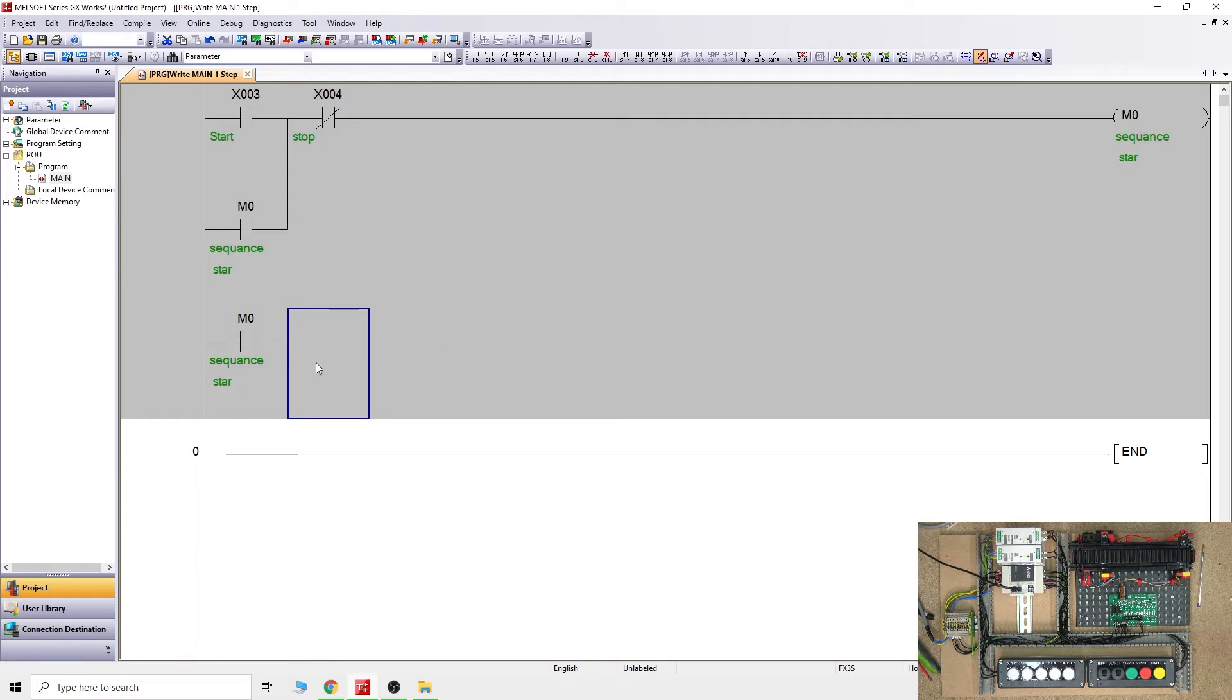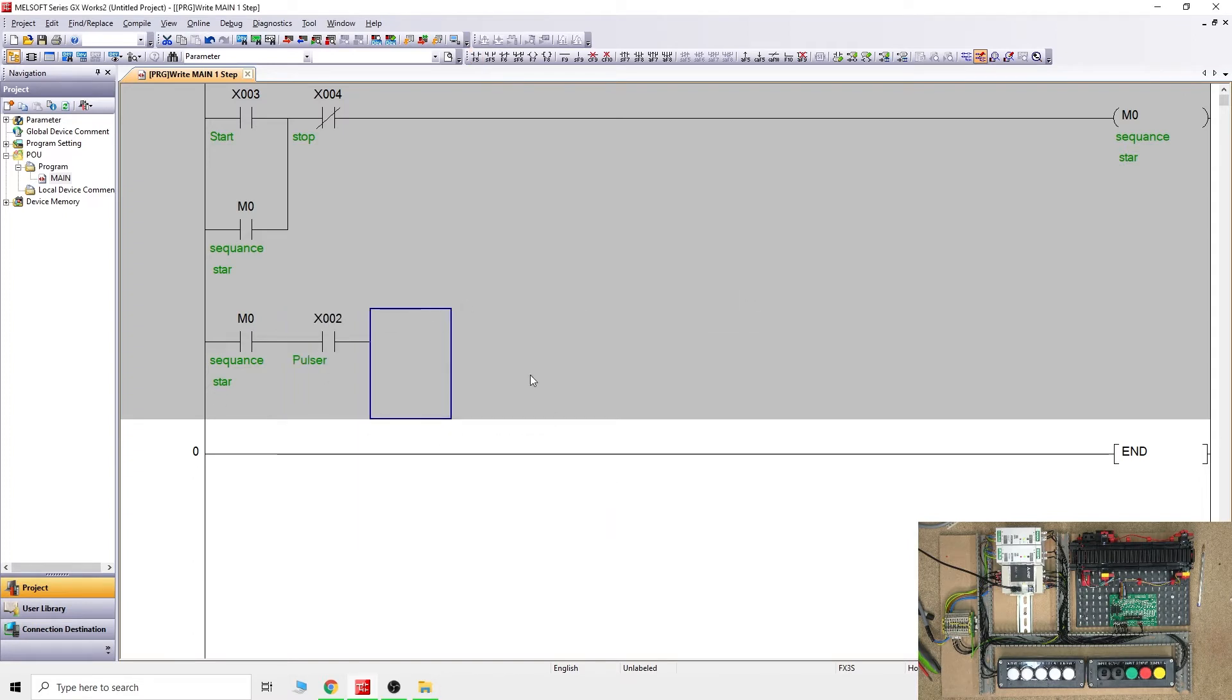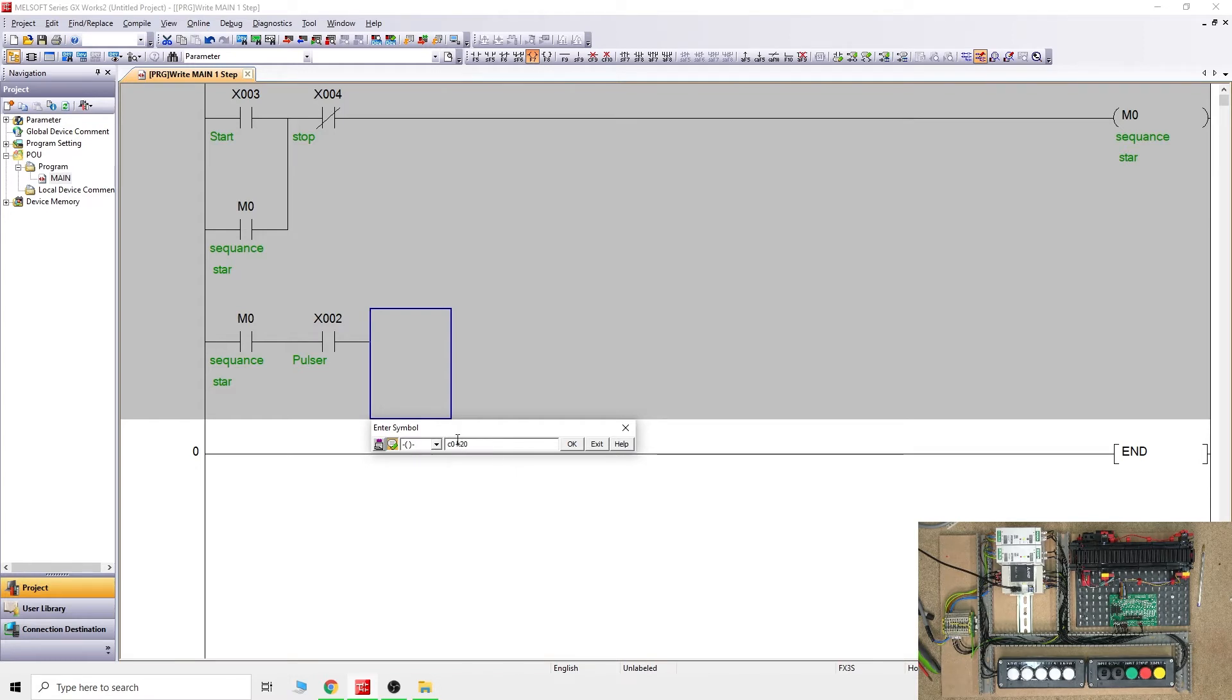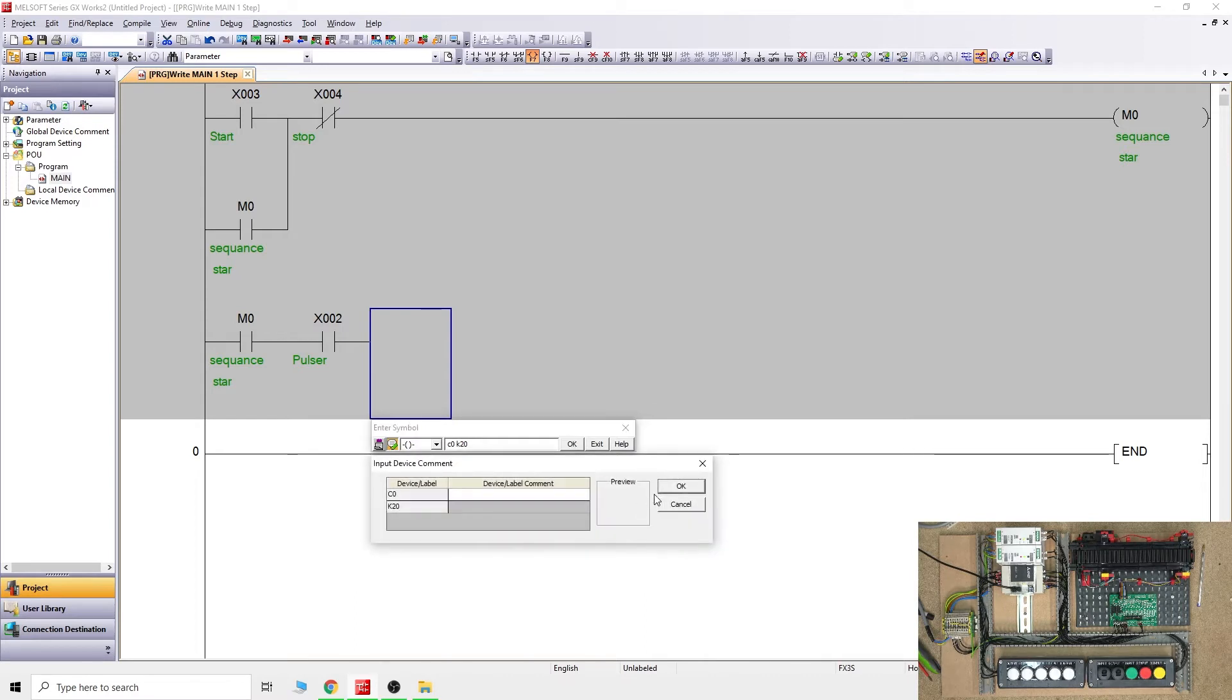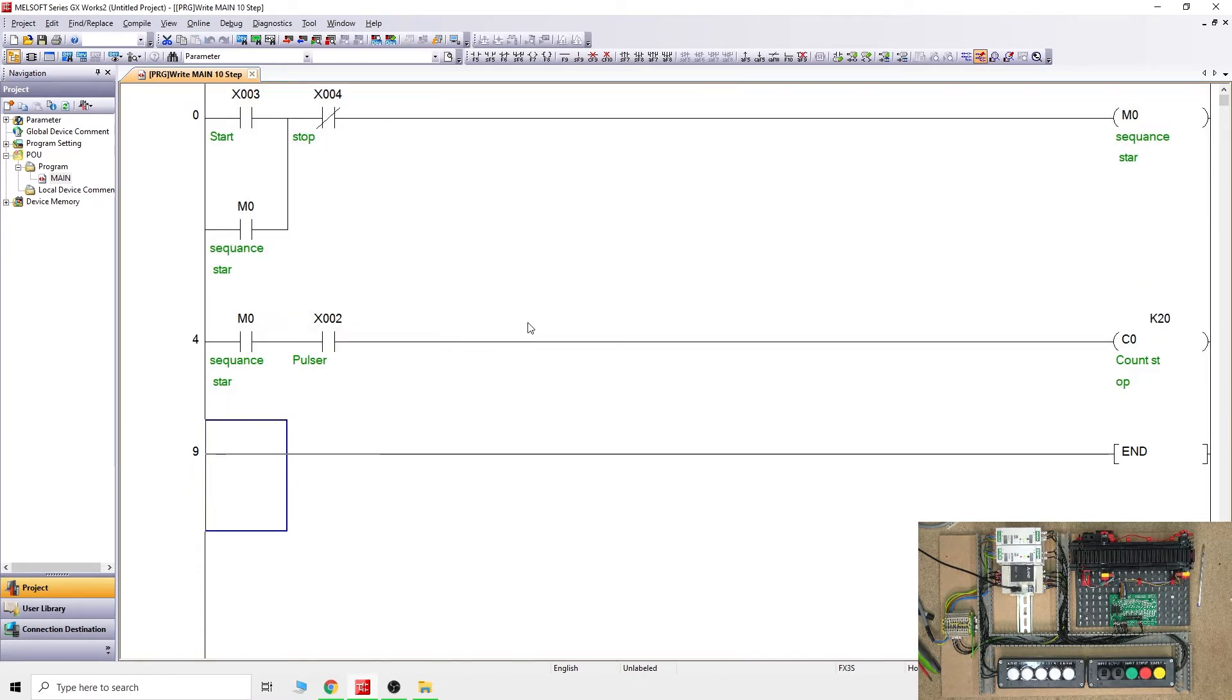From there on, my pulse on my training station is on X2, so we're going to call that contact X2 and call it pulse. Once you do that, we're going to create the counter. A counter is a coil, so we're going to call it the same way as we did with the timers. We're going to say C0 and we'll count till K20.